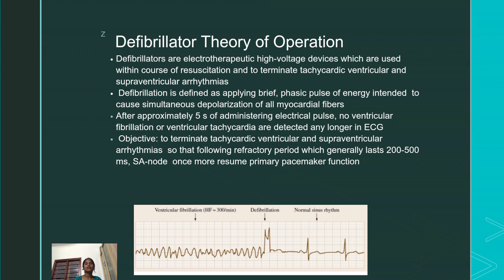After approximately 5 seconds of administering the electrical pulse, no ventricular fibrillation or ventricular tachycardia is detected any longer in the ECG. The objective is to terminate tachycardia, ventricular and supraventricular arrhythmias so that during the following refractory period, which generally lasts 200 to 500 milliseconds, the SA node once more resumes the primary pacemaker function.